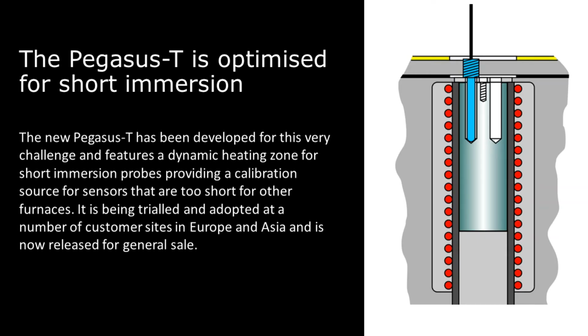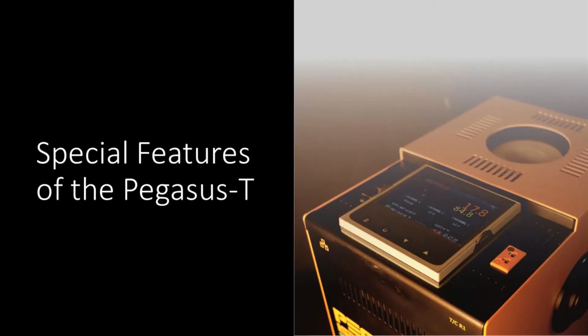The unit has been developed for the challenge of calibrating short sensors. It features a dynamic heating zone for short immersion probes, providing a calibration source for sensors that are too short for other furnaces. It is being trialled and adopted at a number of customer sites in Europe and Asia, and is now released for general sale. Let's have a look at some of the new special features.